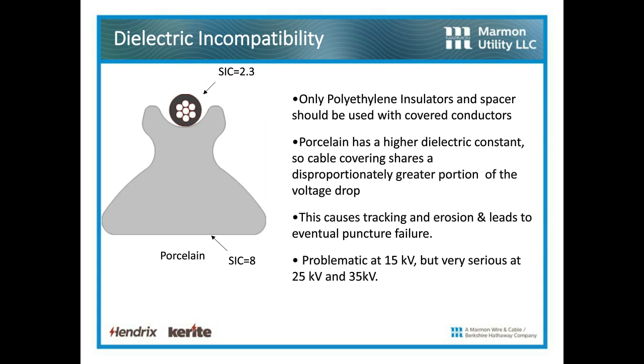Porcelain has a higher dielectric constant, so the cable covering shares a much higher portion of that voltage drop. Again, between that bare conductor and the ground, it's a voltage divider circuit, and it's going to divide in inverse proportion to the dielectric constants. So this disproportionate sharing of that voltage drop is going to cause tracking and erosion and lead to eventual failure. It can be problematic at 15 kV, but it can be more serious at 25, and at 35 kV it can cause a failure within 6 months.